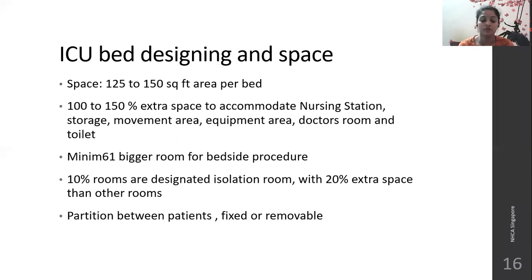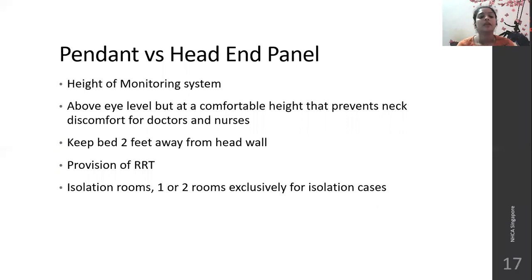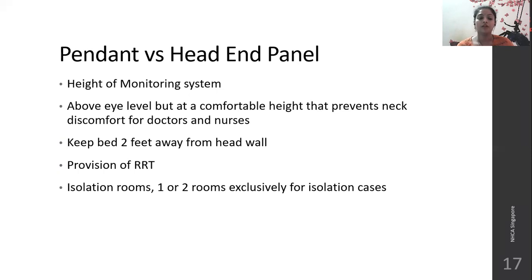Partition between patients should be fixed or removable. The monitoring system can either be a pendant monitoring system — hanging in the center of the ICU — or a head-end panel system where all monitors are placed at the head end of the patient. The monitoring system should always be above eye level but at a comfortable height to prevent neck discomfort. Keep each bed at least two feet away from the wall. One or two rooms exclusively for isolation cases should be provided.